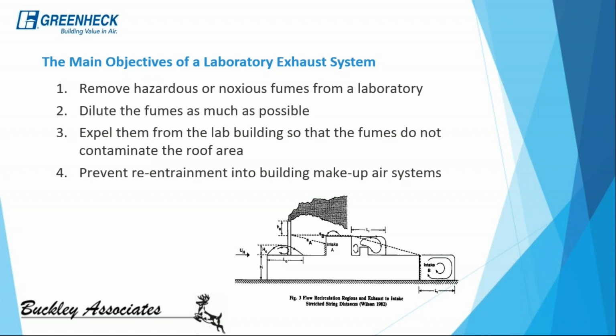And those are: one, removing hazardous or noxious fumes from a lab. Two, we need to dilute those fumes that we're exhausting as much as possible. Three, we need to expel the fumes away from the building so they do not recontaminate any of the roof area. And then three and four are kind of similar. We need to prevent any makeup air units from pulling that exhaust air back into the building.